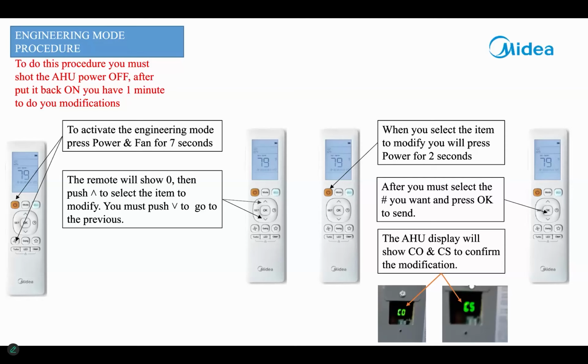If you fail to press a button within 30 seconds, it will back out of engineering mode automatically and your parameters will not be saved. And realistically, using a communicating thermostat, communicating air handler setup, how often will we be in there outside of diagnostic and looking at settings? How often will we be in engineering? Realistically, it's not going to be very often. Okay. So that's going to be case by case, installation by installation basis.